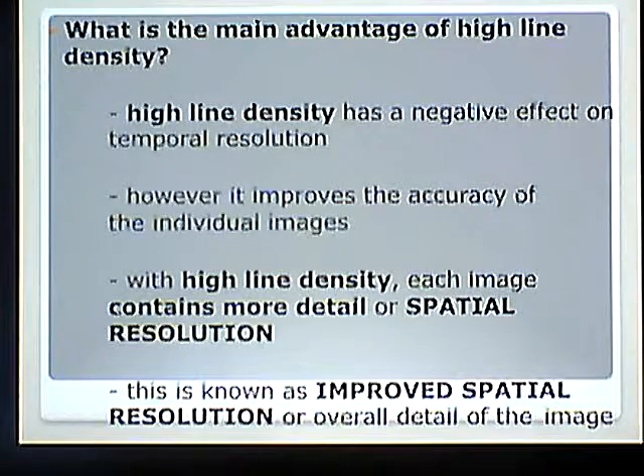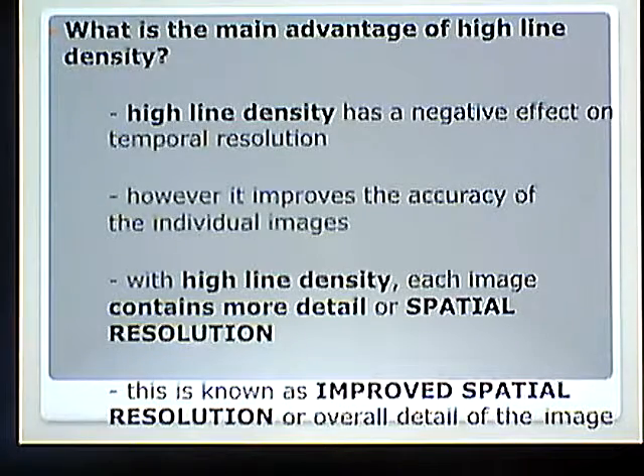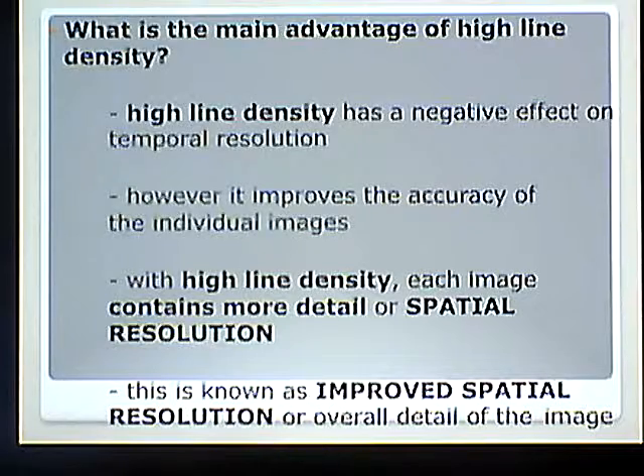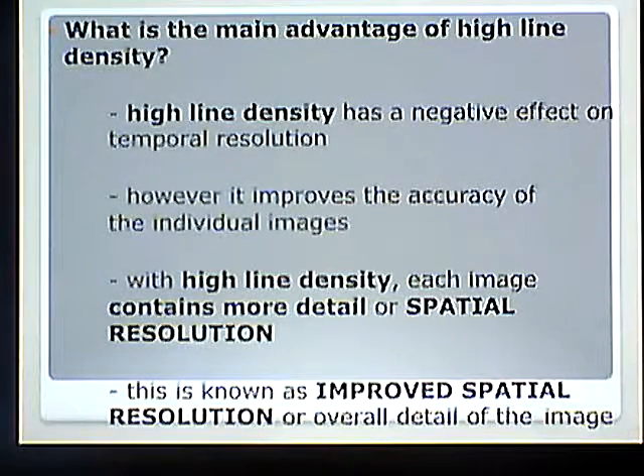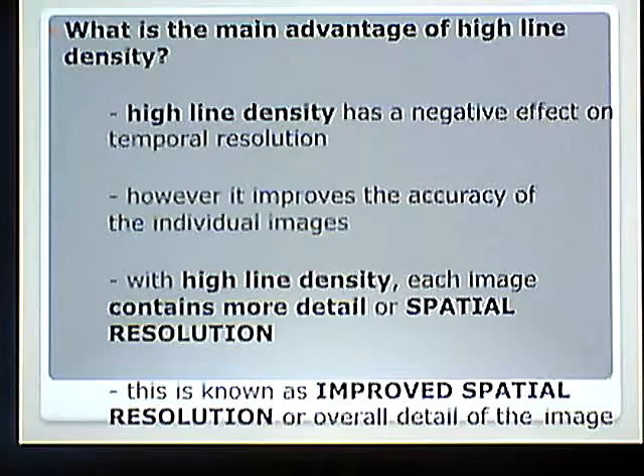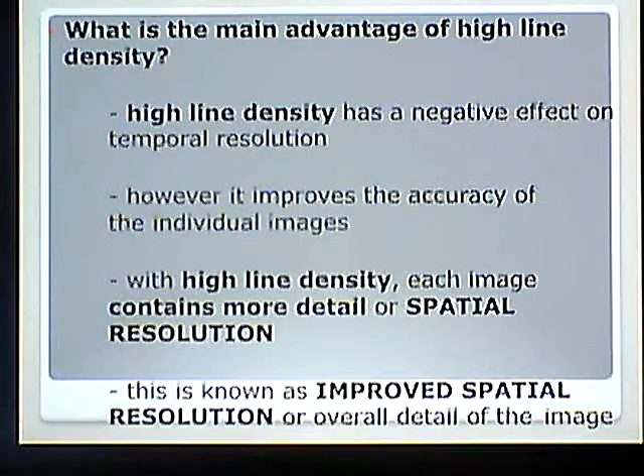What is the main advantage of high line density? High line density has a negative effect on temporal resolution — it slows things down. However, all those pulses tightly packed together improve the accuracy of individual images. It's like going from a 2-megapixel camera to a 20-megapixel camera — super detailed. With high line density, each image contains more detail: this is known as improved spatial resolution.